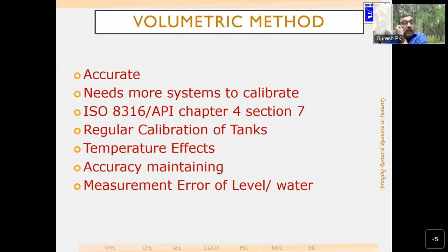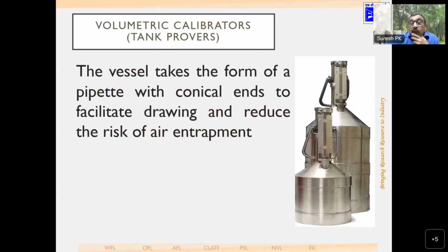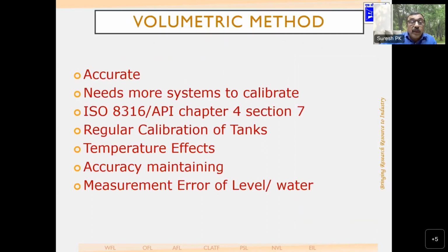So when you are saying volume tanks, how do you calibrate the volume tanks? If you have a 10-liter volume tank, then you need to use maybe a smaller volume tank to calibrate it, and then finally it reaches the pipette or a specific gravity bottle, and the specific gravity bottle is calibrated using a weighing machine. Basically, it goes back to the gravimetric system in the end.